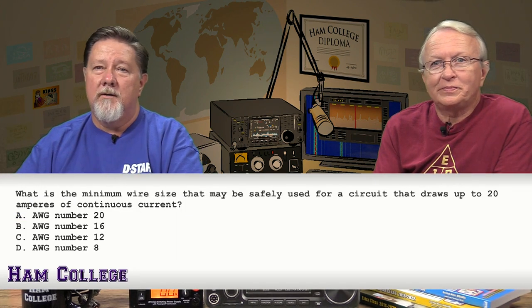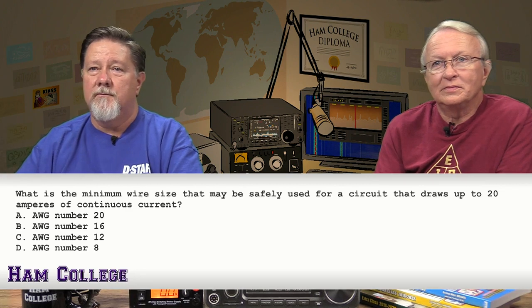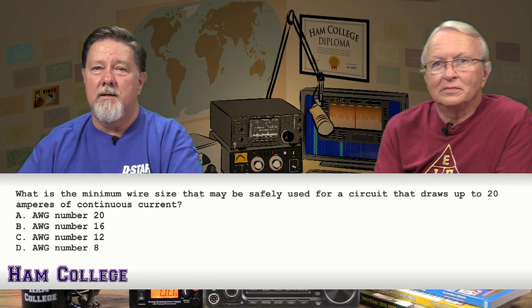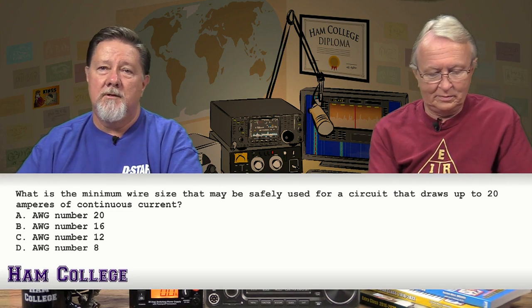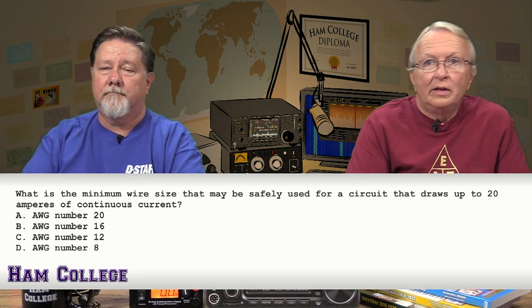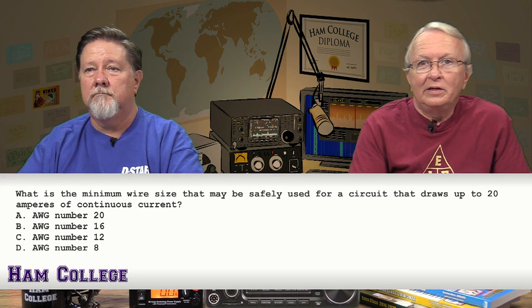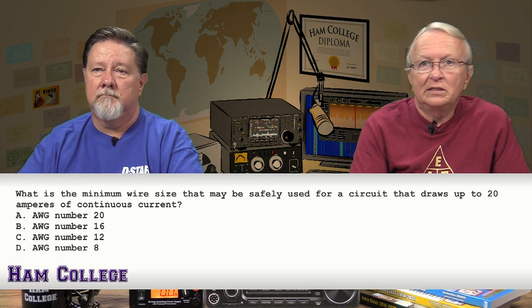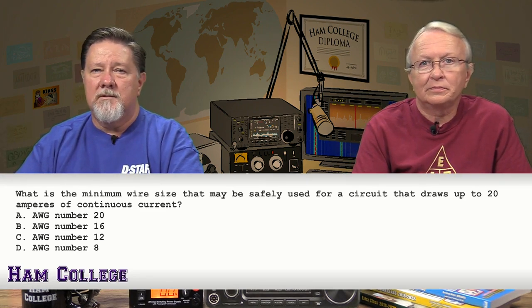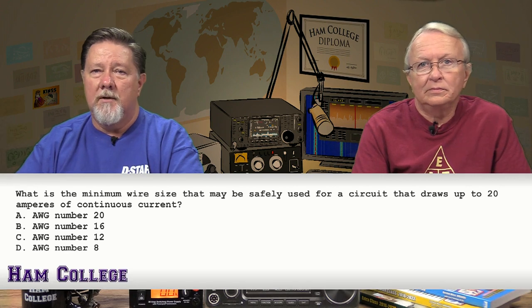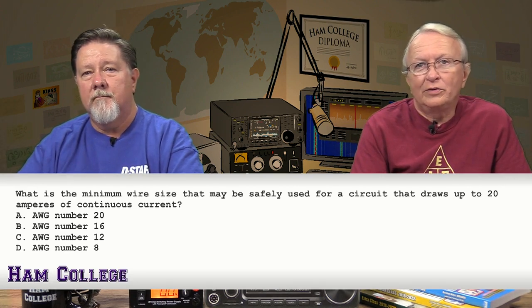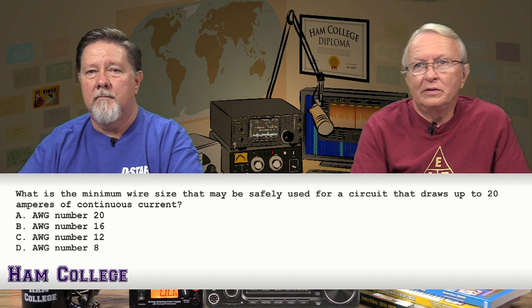What is the minimum wire size that may be safely used for a circuit that draws up to 20 amperes of continuous current? A, AWG number 20. B, AWG number 16. C, AWG number 12. Or D, AWG number 8.